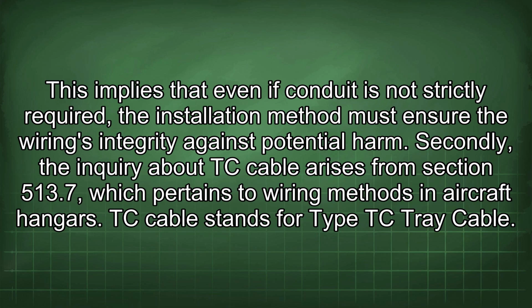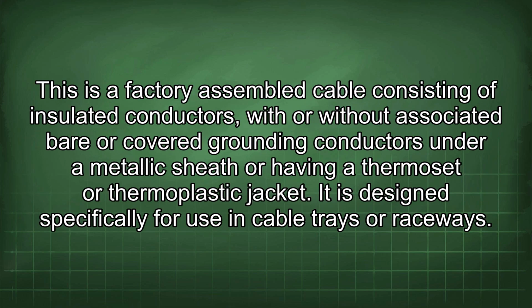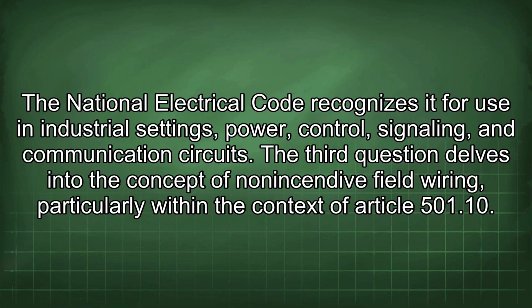TC cable stands for Type TC tray cable. This is a factory-assembled cable consisting of insulated conductors, with or without associated bare or covered grounding conductors, under a metallic sheath or having a thermoset or thermoplastic jacket. It is designed specifically for use in cable trays or raceways. The National Electrical Code recognizes it for use in industrial settings, power, control, signaling, and communications circuits.